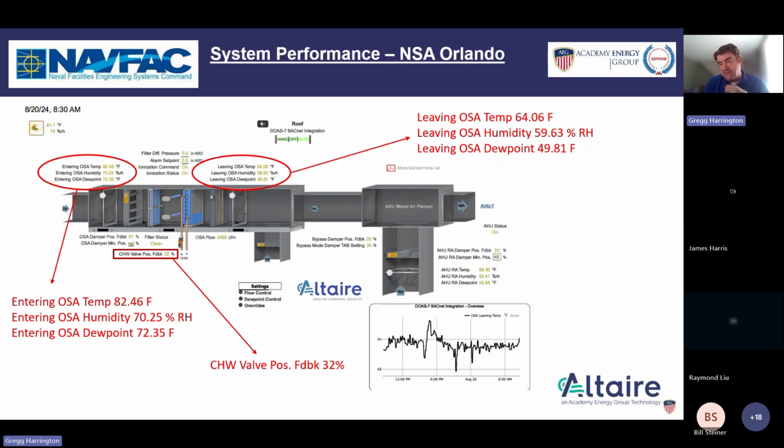And we were able to sufficiently keep a 300,000 square foot building in the appropriate dew point set points in the building without any additional reheat or independent reheat through the high part of Florida humidity season. Does anybody have any questions relative to this project?